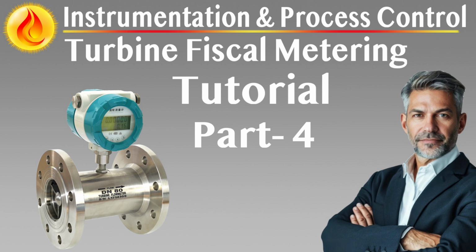and repeatability. The prover must include a quick opening closure to facilitate safe and efficient insertion and removal of the prover sphere, or piston. The number of pulses counted during one calibrated run must exceed 10,000 to ensure high resolution in the K-factor calculation.